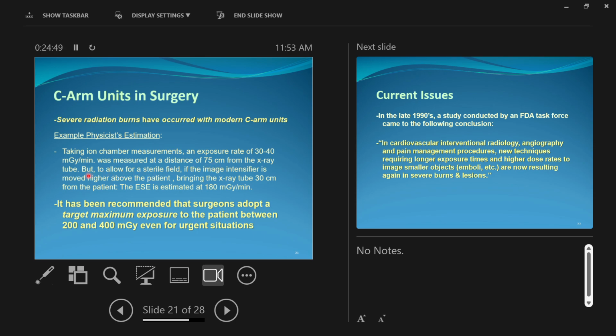To allow for a sterile field, the image intensifier is moved high above the patient. Again, image receptor and X-ray tube are a fixed distance from each other. So if I need to move my image receptor up, the X-ray tube is going to come closer to the patient. It's underneath the patient. Patient's here-ish. And we come up with the X-ray tube and higher with the image intensifier, image receptor. So in order to get the image receptor, or as they're calling it, the image intensifier, high above the patient, the X-ray tube comes very close.